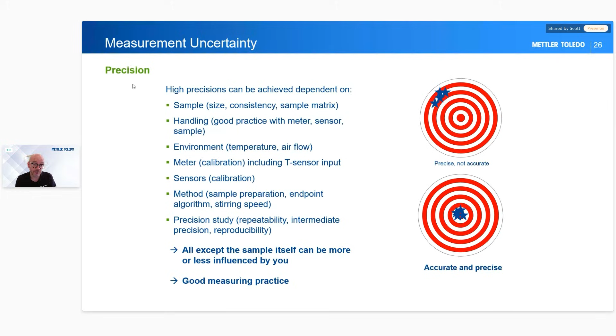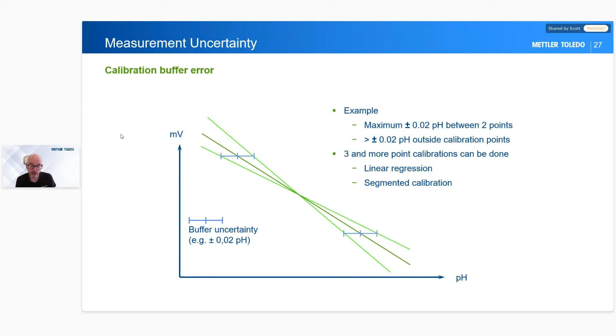I've got 2 examples here of some uncertainty in the systems already. So we gave a big long list, but one of these is calibration buffers. When you're using buffers, go back to your labs this afternoon and look at the bottle or the sachet, and you'll find there's actually a plus or minus of a pH involved in buffers. So even when we're taking measurements with buffers, if your buffer has an uncertainty of, say, 0.02, then you're already introducing that kind of buffer error into your system and your measurements before you've even started.